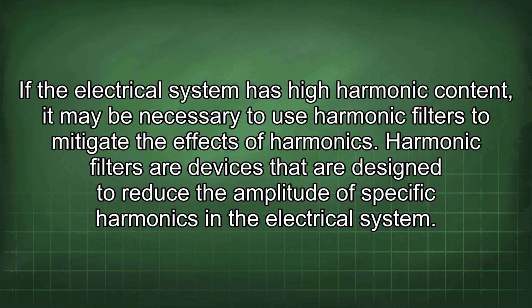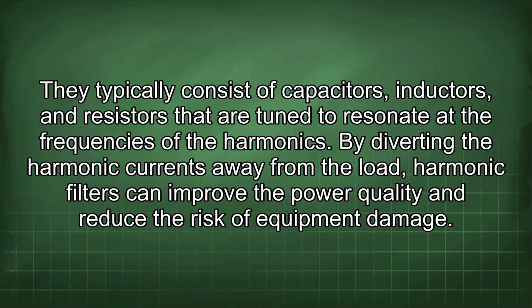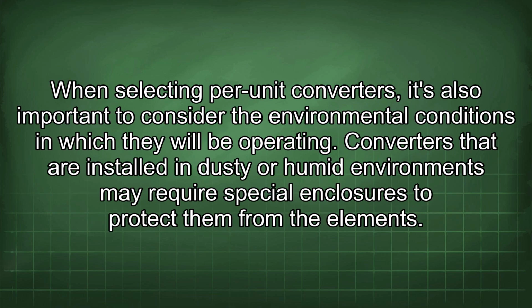If the electrical system has high harmonic content, it may be necessary to use harmonic filters to mitigate the effects of harmonics. Harmonic filters are devices that are designed to reduce the amplitude of specific harmonics in the electrical system. They typically consist of capacitors, inductors, and resistors that are tuned to resonate at the frequencies of the harmonics. By diverting the harmonic currents away from the load, harmonic filters can improve the power quality and reduce the risk of equipment damage.